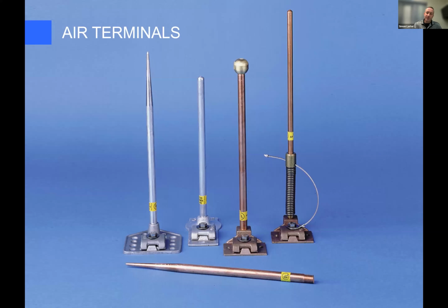Those are the actual lightning rods. They come in various models. The ones on the left, that left-hand one, it's an aluminum rod. We use copper and aluminum in different situations. If moisture is introduced, copper will cause corrosion on exterior galvanized steel surfaces. It will make it rust a whole lot faster. Same if it's just painted steel, metal parapet copings, that happens quickly.